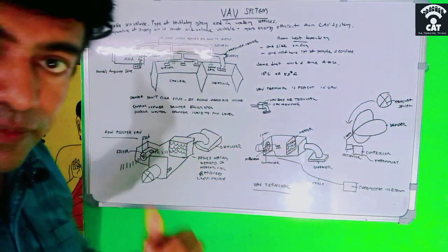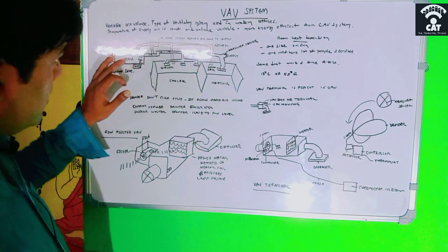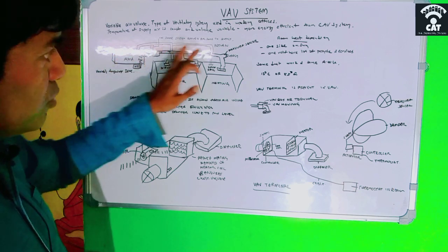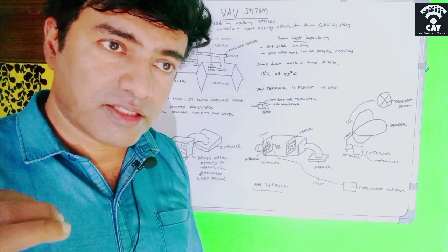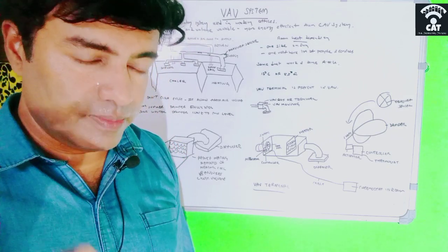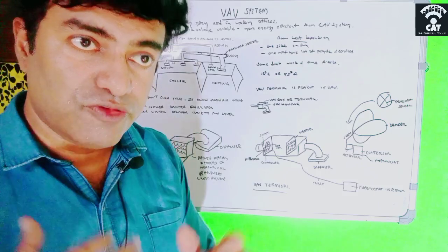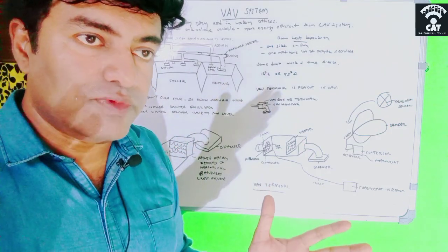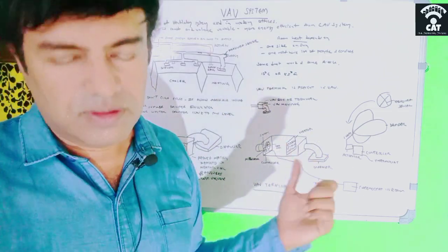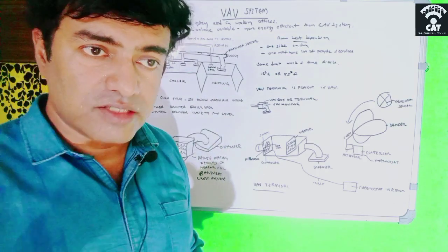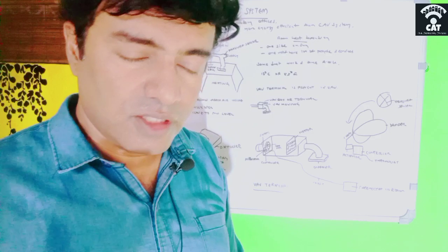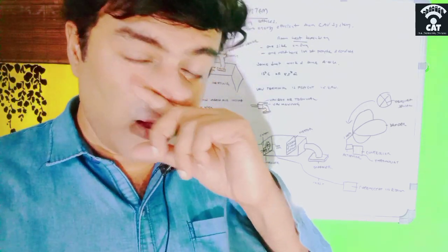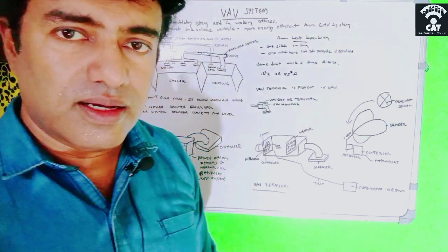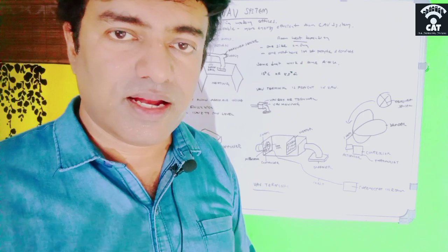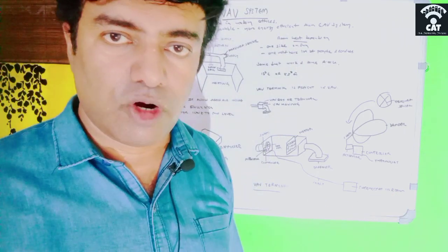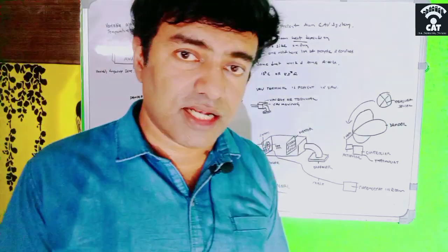And regarding the pressure, I will say one more thing. See, this is the entire system. There is a fan inside the AHU which will supply the air into the full duct system. The supply air is totally controlled by the big fan inside the AHU. So there is a high chance that there will be a pressure difference in the supply system. If there are 6 rooms and all the rooms need the fresh or cold air supply throughout the day, the fan may not handle the system, because it would have to work at full speed all the time, which may not be needed, because some of the rooms may not be occupied. So in such cases, there is a chance of a pressure variance.